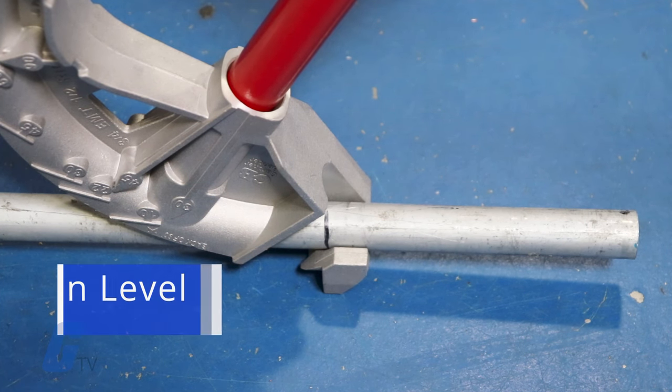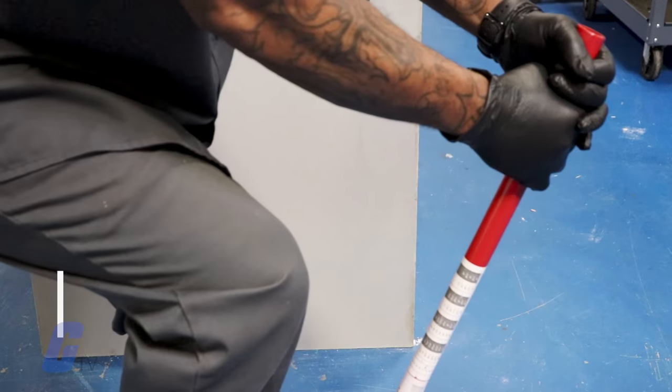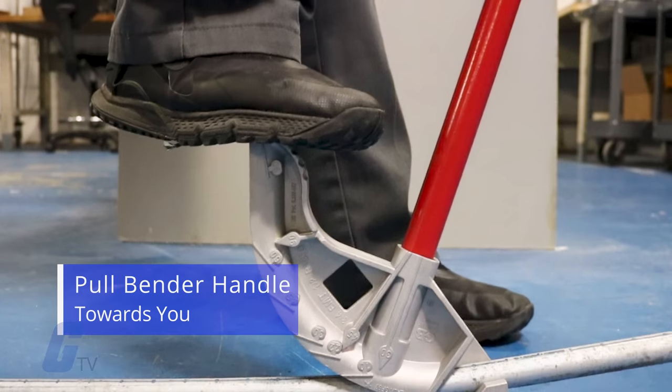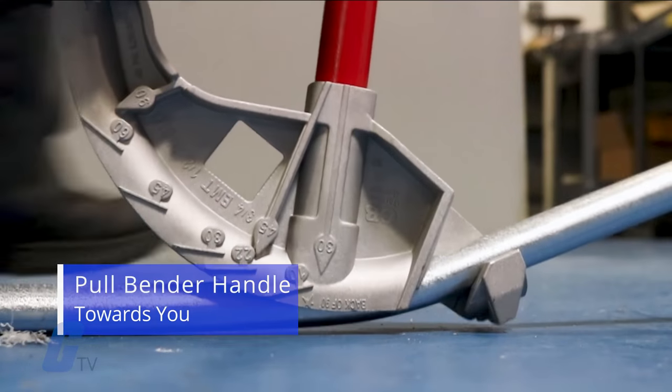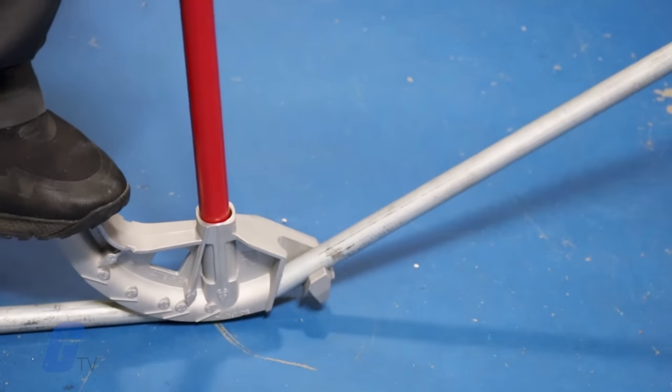Set the conduit on level, firm ground, and place your foot firmly on top of the foot pedal of the bender. Now, pull the bender handle towards you to create the bend with a firm and steady motion to avoid any kinks or crimps in the conduit.